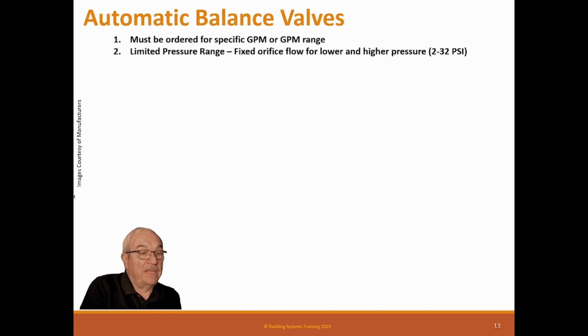This is where, as a balance contractor, you need to actually look at these. And most people say, oh, I've got automatic valves, you don't need to balance at all. That's not true. You need to balance the pump, and you need to verify the pressures in the field do not exceed the limits of these valves. If they exceed them, you have to have a valve in front of them to balance them down, so the valve won't see the maximum pressure. Or else you can just let it be an orifice, either way. They do come in different ranges. Some are 1 to 14. I think there's a 5 to 50 psi. There are different psi ranges, but I don't think most contractors know that. They just install them because it's automatic. They say, I don't need to buy balance. They actually do. It just should be a lot cheaper.